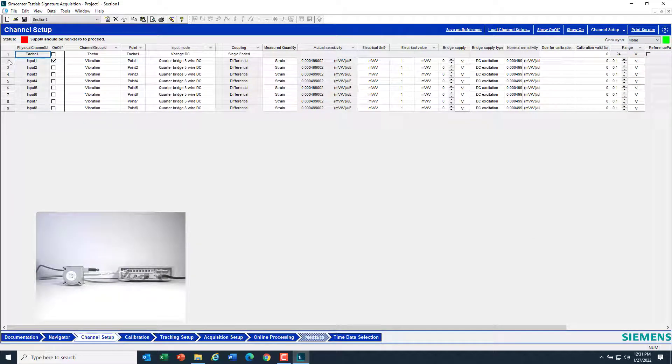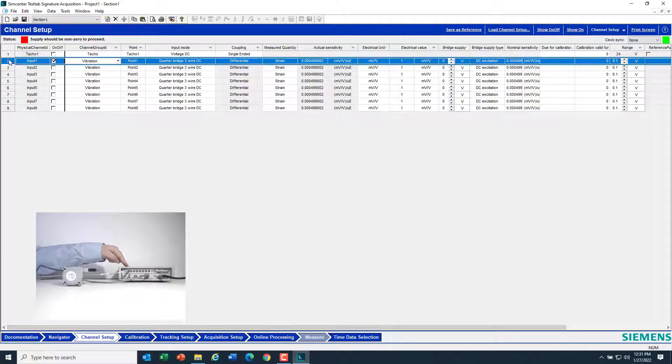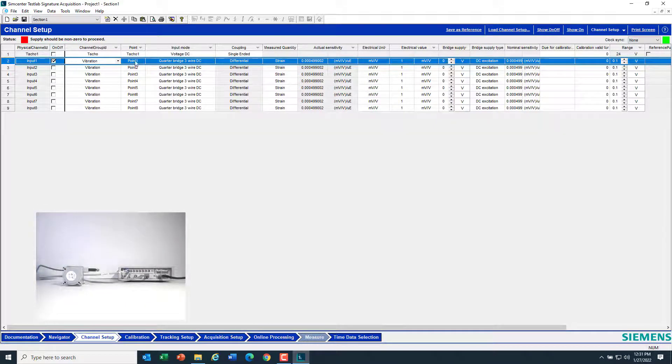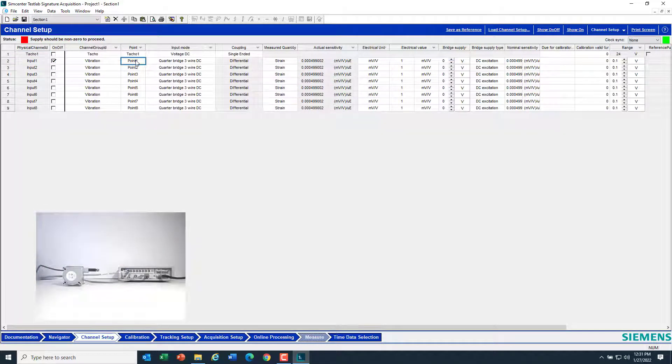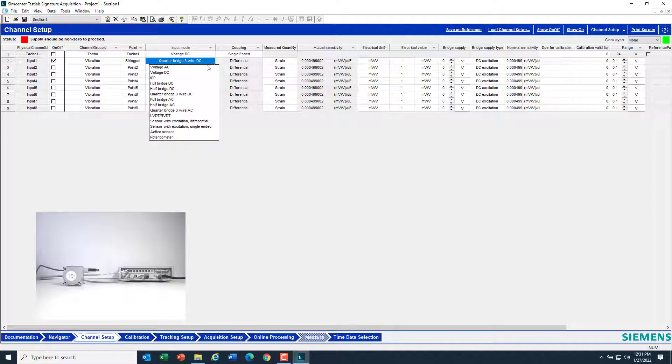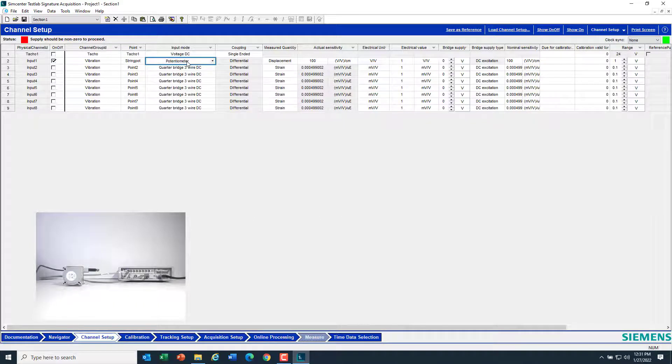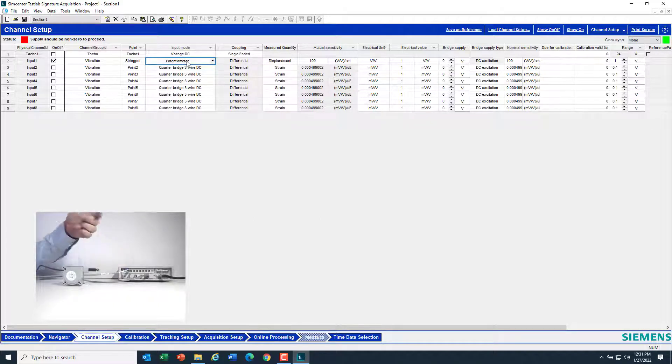Here I have my string pot attached to channel 1, which is input 1 over here. I'll type in a name, String Pot, so I know what that channel has on it. Under Input Mode here, I'm going to pick Potentiometer. Pot and String Pot is short for Potentiometer, so this is a VB8 card that has special mode to support string pots.